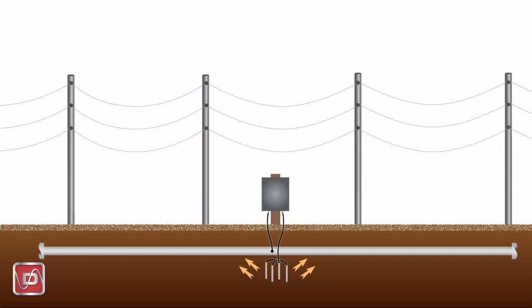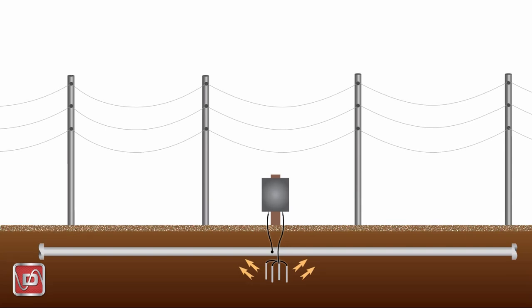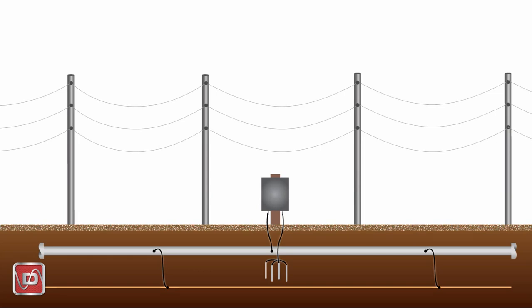Let's install a continuous mitigation system using zinc ribbon to drain the induced AC and provide safety grounding for any faults or lightning current that our pipe might encounter. Unfortunately, we solved one problem but created another.